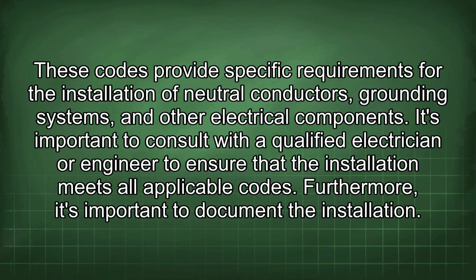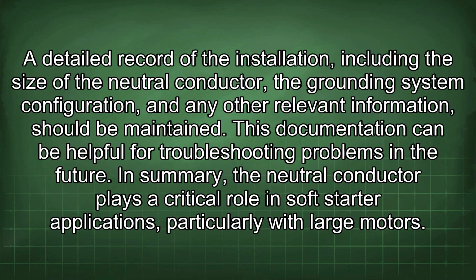Furthermore, it's important to document the installation. A detailed record of the installation, including the size of the neutral conductor, the grounding system configuration, and any other relevant information should be maintained. This documentation can be helpful for troubleshooting problems in the future. In summary, the neutral conductor plays a critical role in soft starter applications, particularly with large motors.